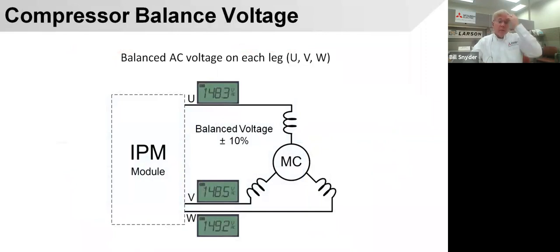And if you take that compressor and you measure across U, V, and W, you should get very, very similar voltages. It should not be more than 10% variance between U and V, U and W, and V and W. Just like you would ohm out a three-phase compressor or check the voltage going to a three-phase compressor. We would do it the same way.